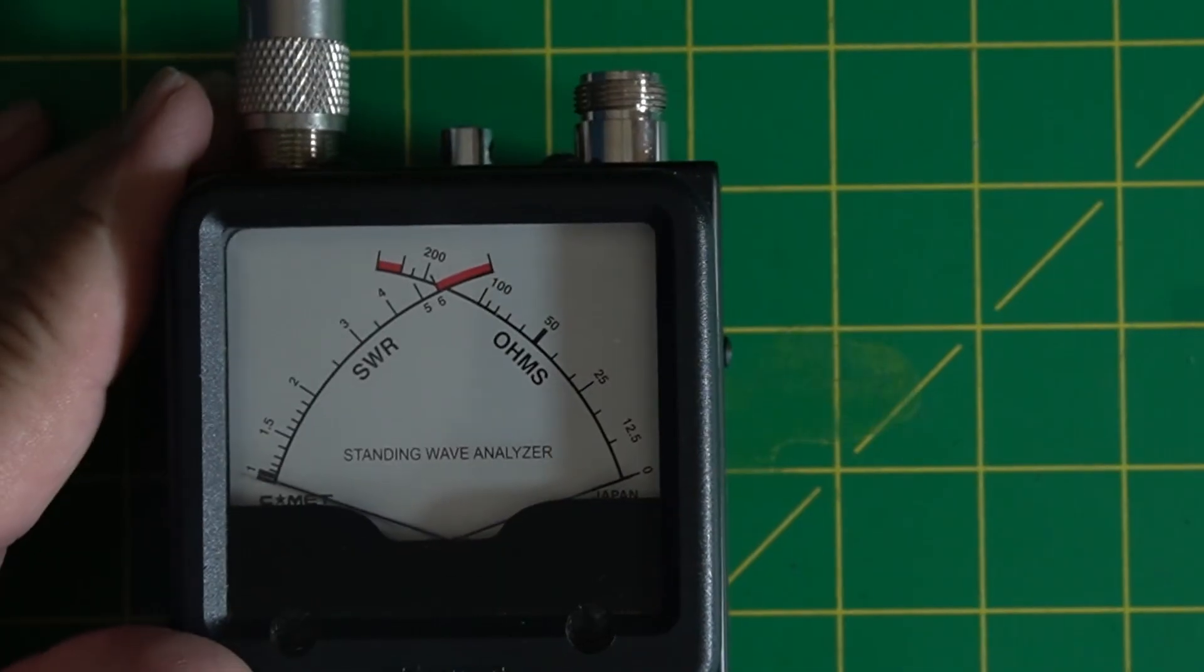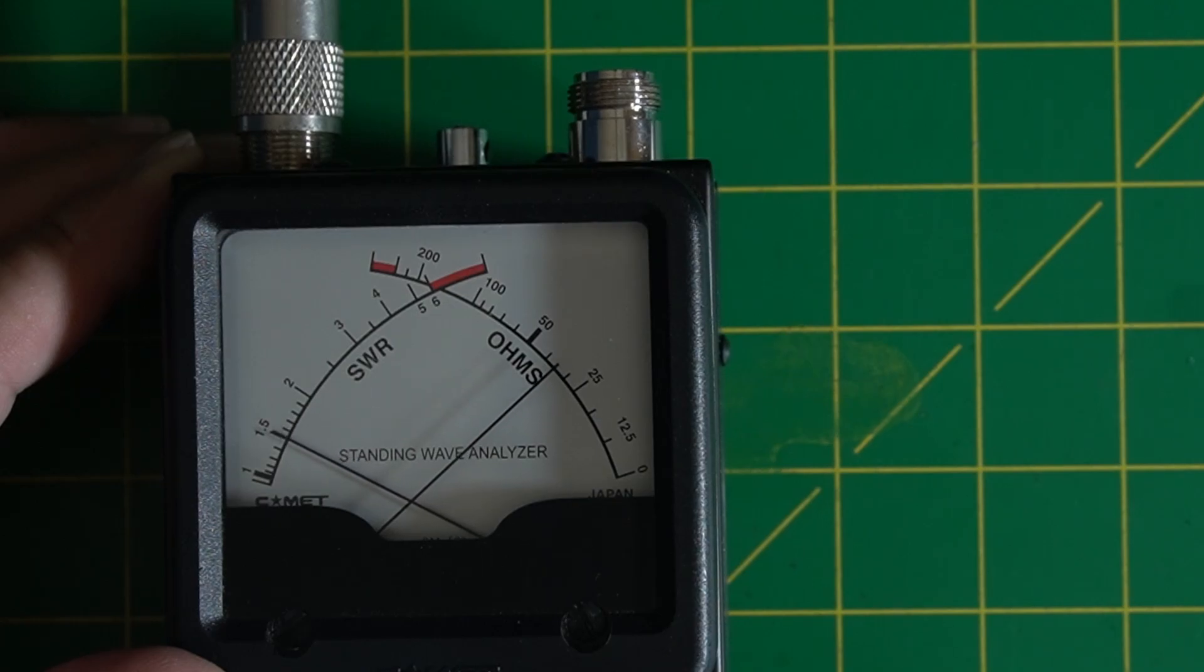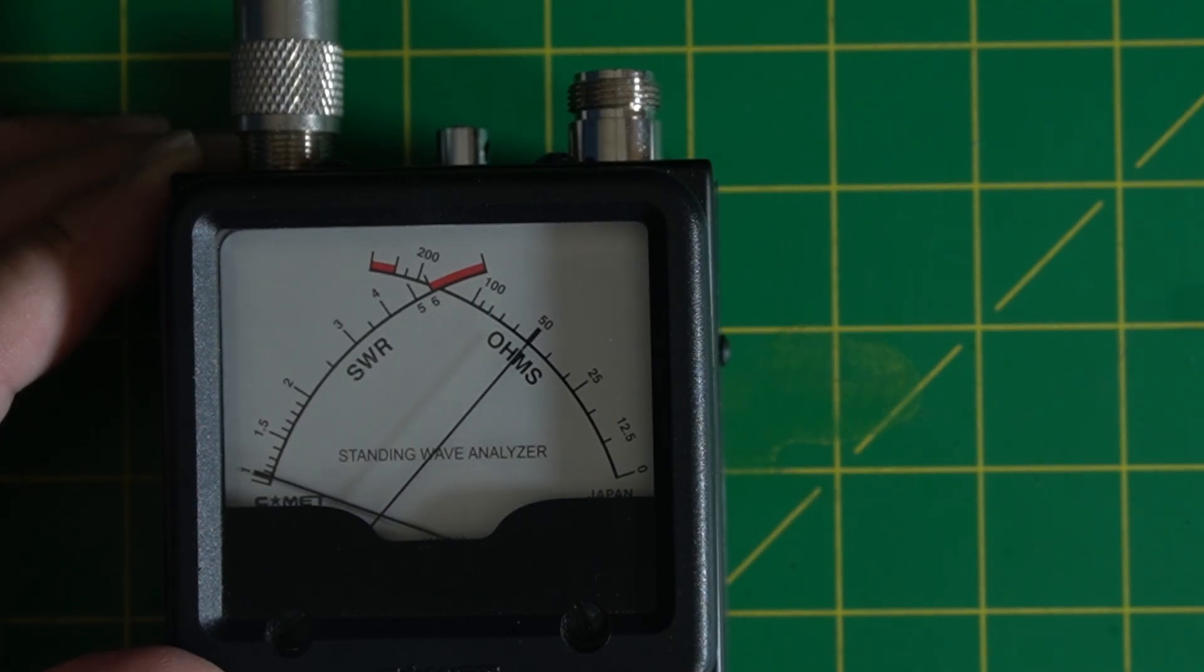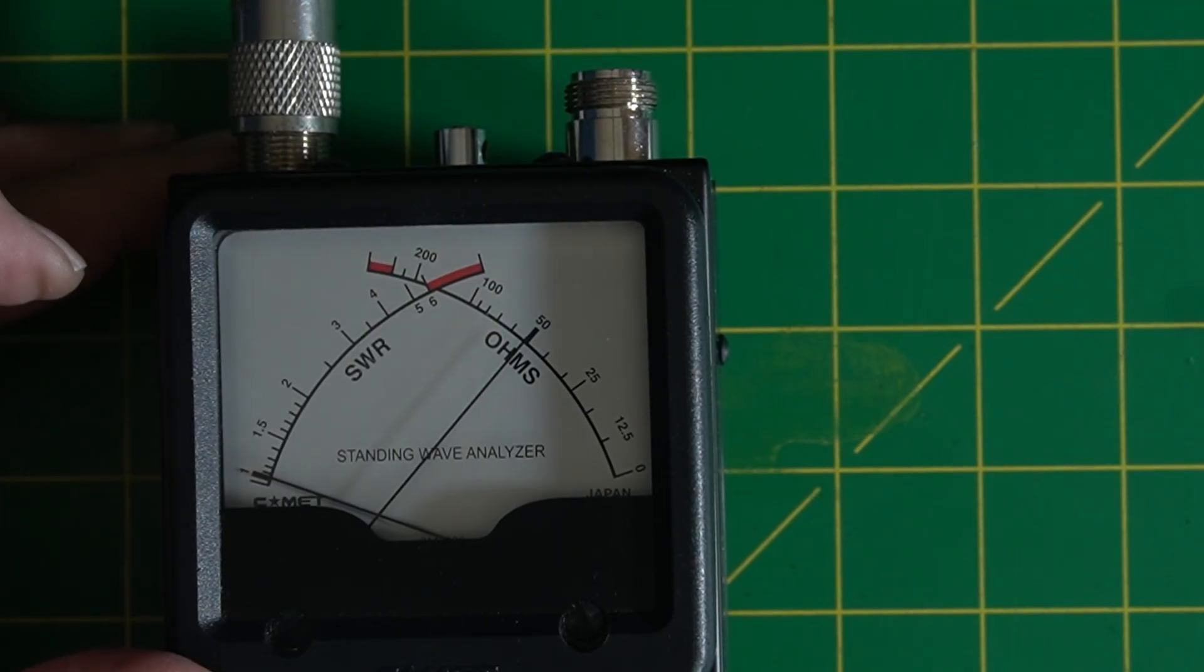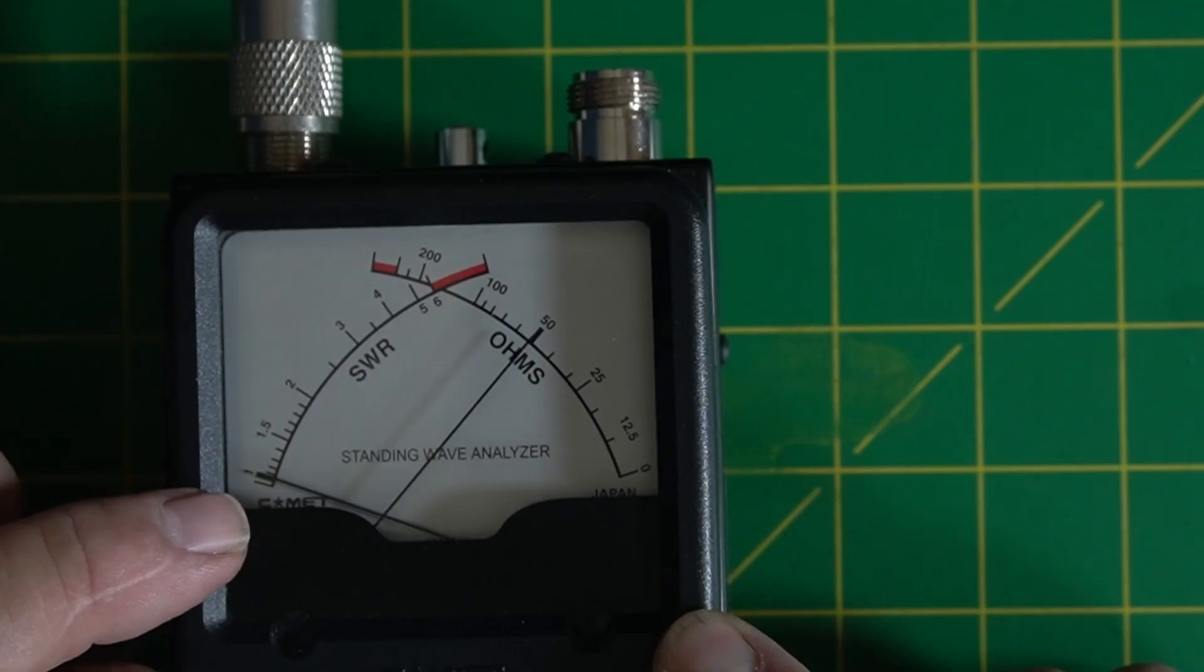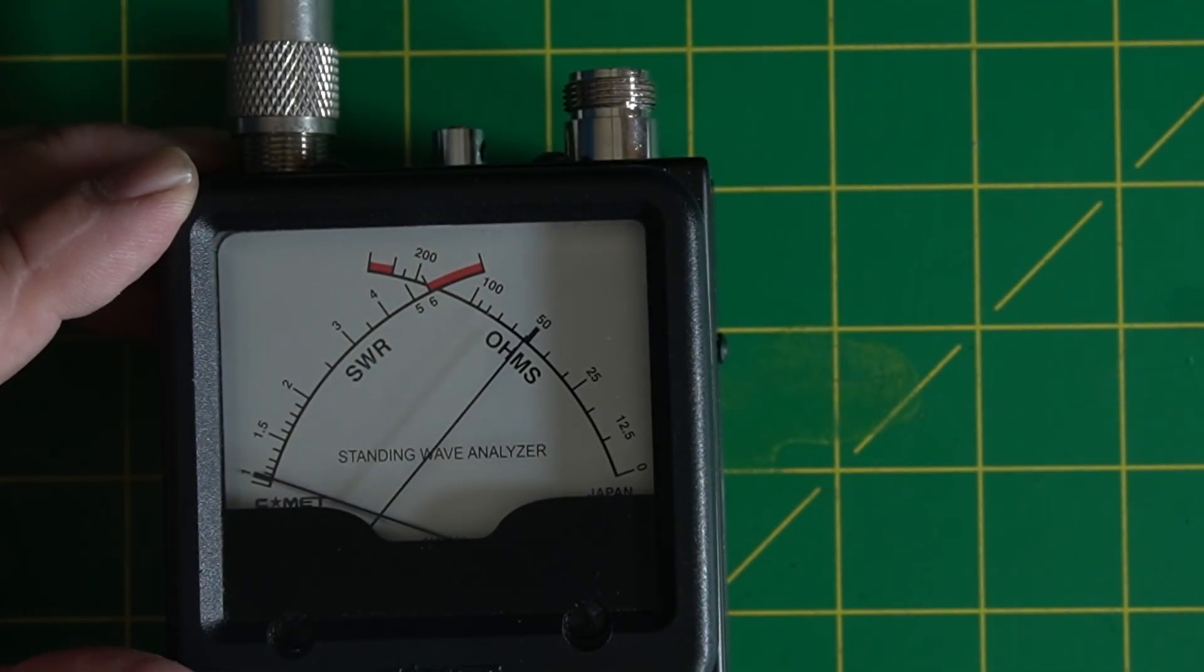I had this thing hooked over here. So let's just do this. Let's turn this on. So we were at 14.190. Let's go to 14. 14. Pretty close. 192. And on here we have 1.0, which pretty much is what we had. And you can see on the meter there. I don't know this. I think this has a light, but I'm going to turn it on right there. It's really small and we're 50 ohms there. So pretty close.